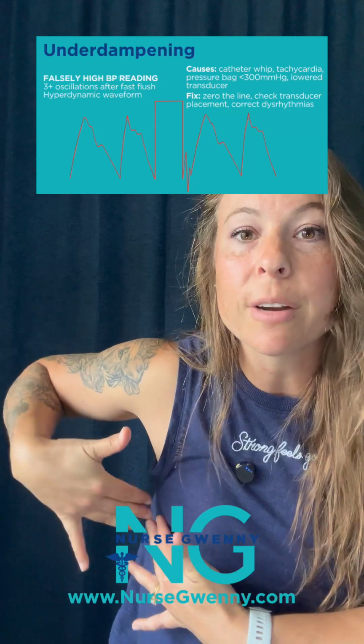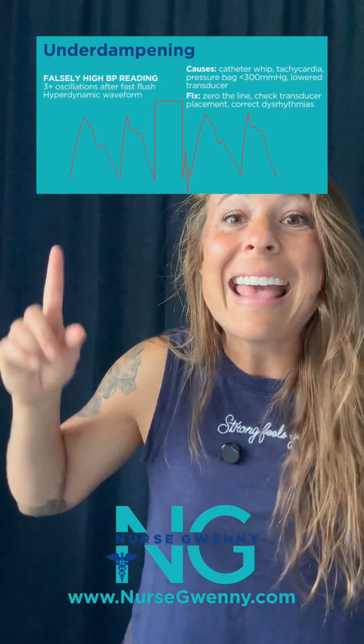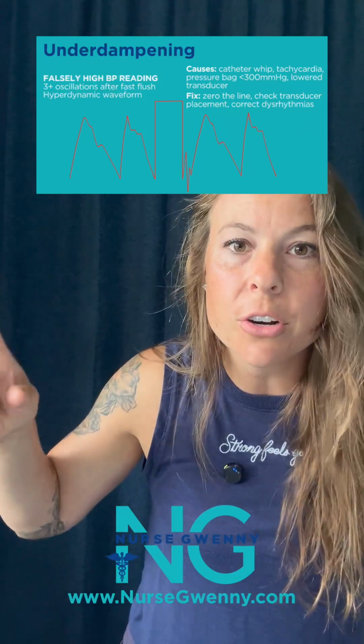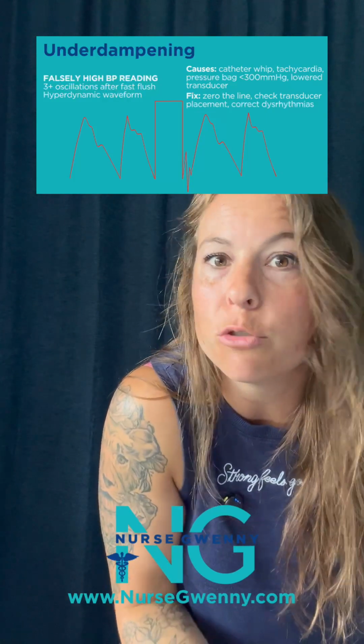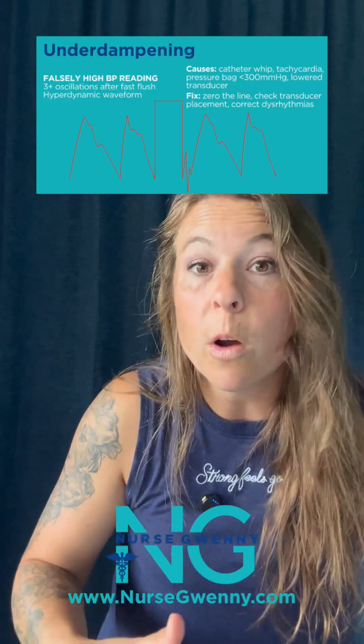We want to make sure our transducer is where it should be, and that our pressure bag is set to 300 and it hasn't all of a sudden accidentally been dropped down to 150, which when we're talking about flight physiology, this is where Boyle's law comes in, because that pressure bag that we keep around that bag of fluids is influenced by changes in altitude. So it's really important to manage all of these different things when taking care of an art line. Look, there's a lot more you need to know, but this is just Art Line 101 in about 6 minutes.